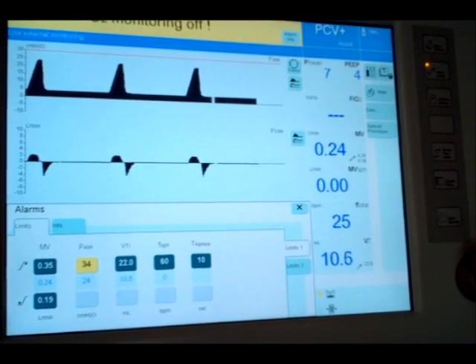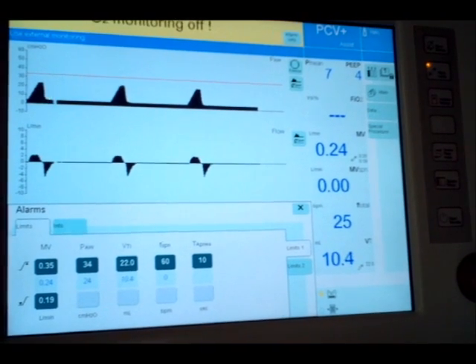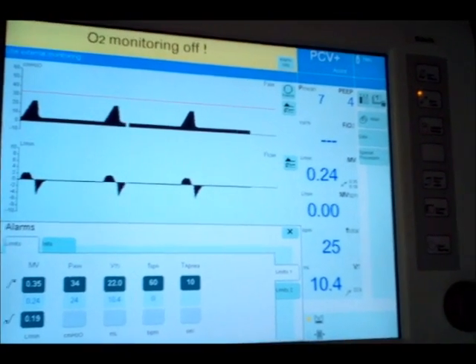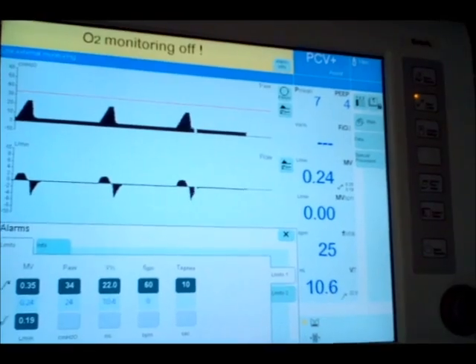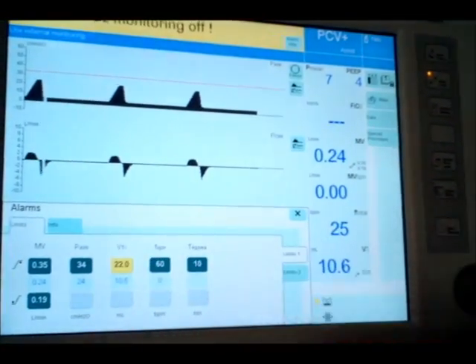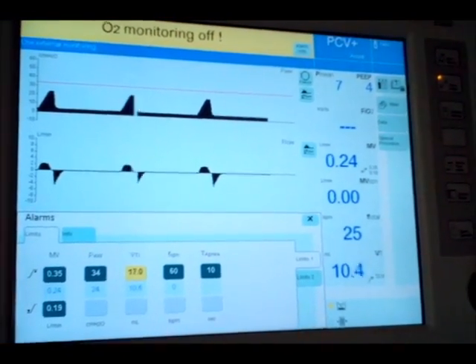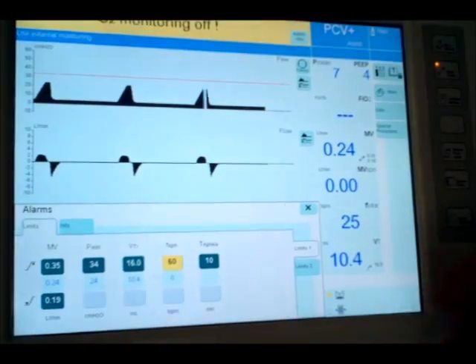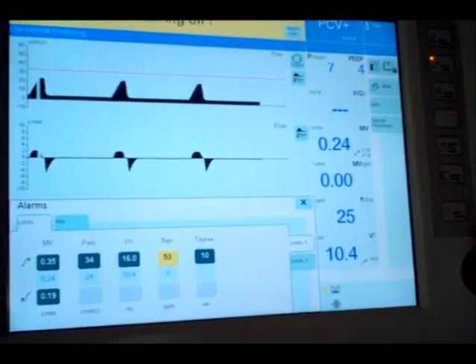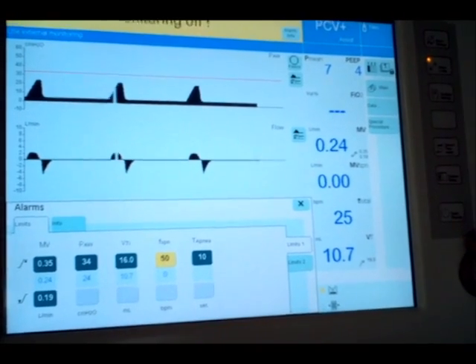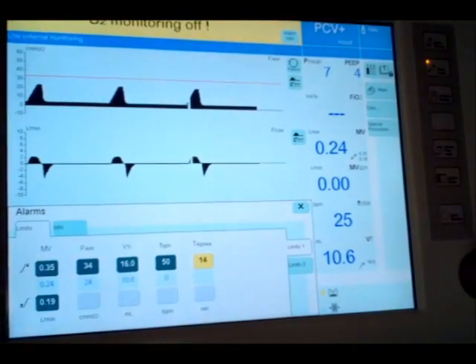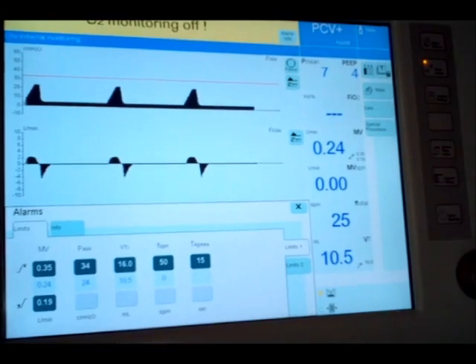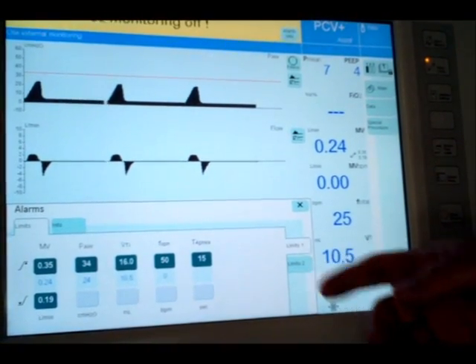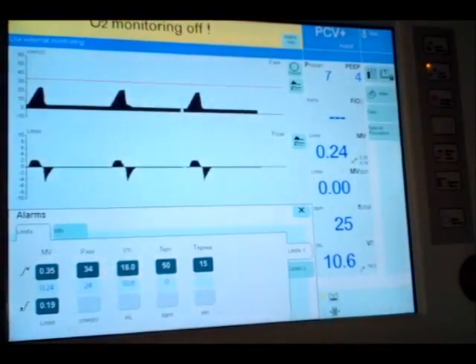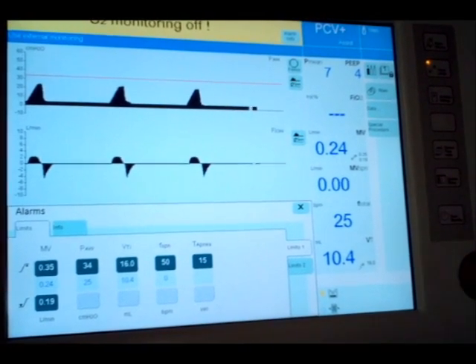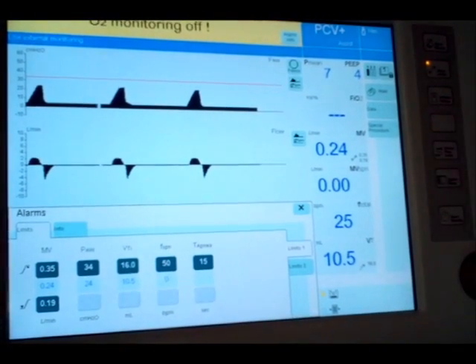There's really no real reason, because this is pressure targeted, there's no real reason for our PIP to be any higher than our setting, other than something being wrong. Inspiratory tidal volume, we're getting 10, so I'm going to turn this down to maybe 16. That's not going to apply really in this mode. I'll just get ready for the next mode. I might back off in my apnea time since CO2 is the only thing on. We're not going to deal with that this semester, so don't worry about limits 2 here or alarms 2.